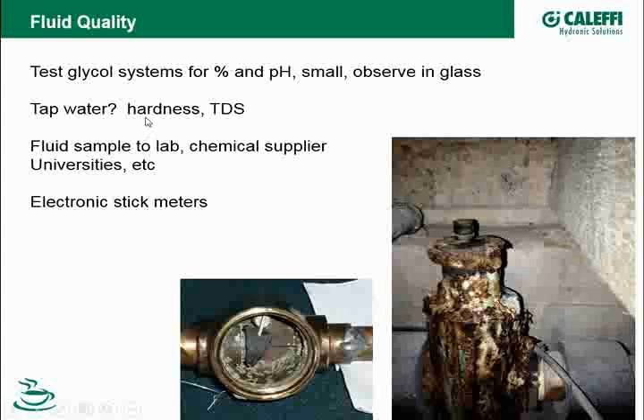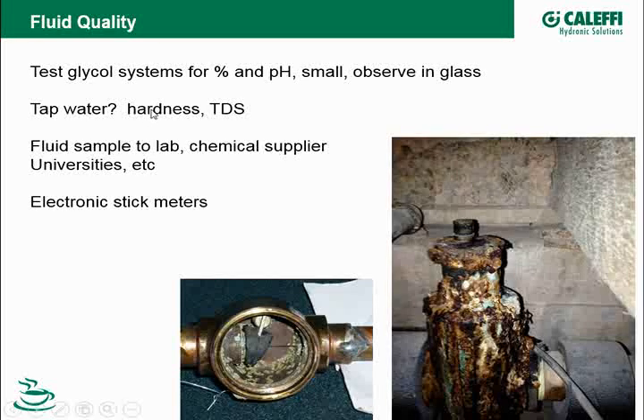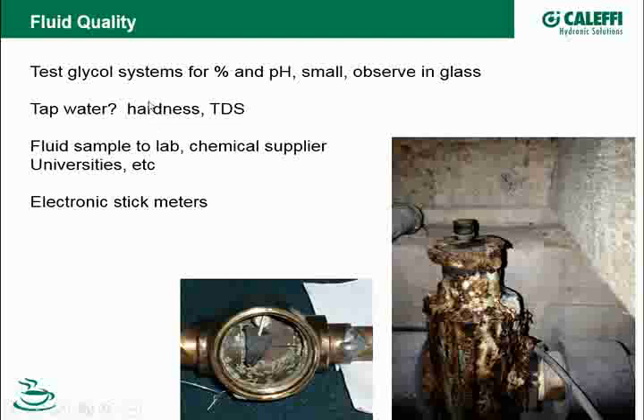You'll notice most of the boiler manufacturers now are putting that right in their installation information. They're going to put a water quality, and it'll tell you the hardness that's acceptable, the TDS, the pH of the water, chlorides, especially if you're using stainless steel boilers or stainless steel coils in your indirect tanks. The chloride level is pretty critical to that. So I think I've got a slide coming up.